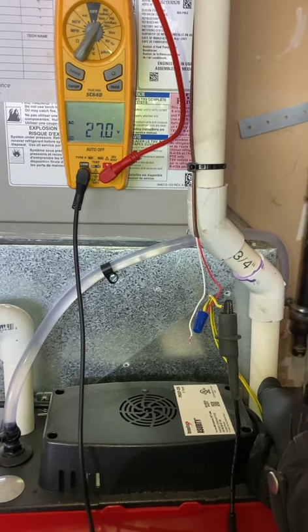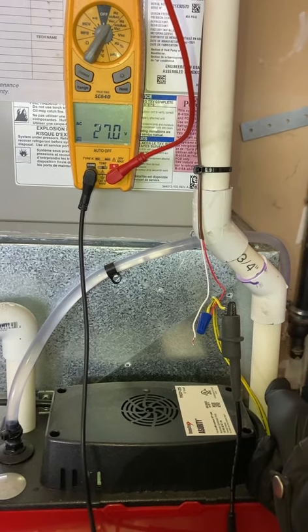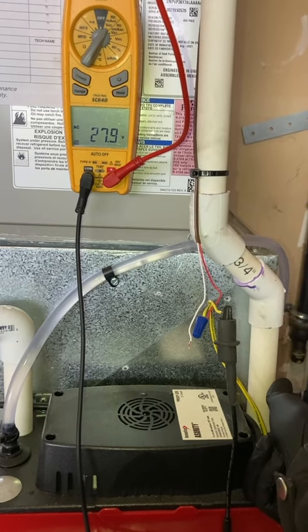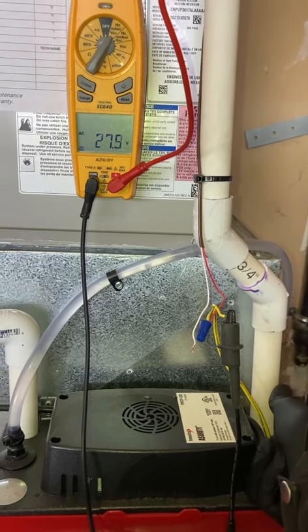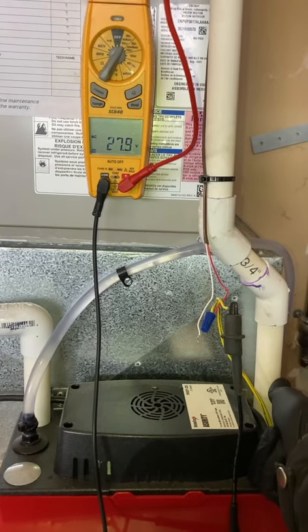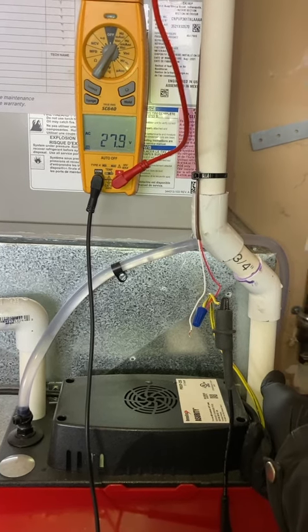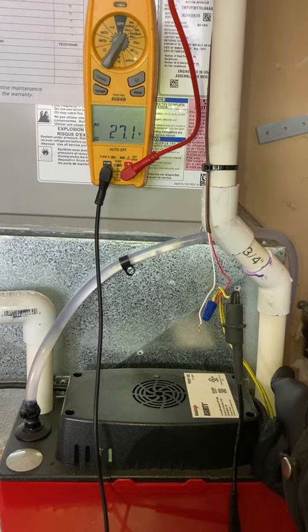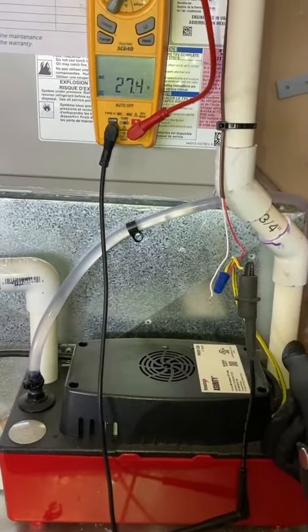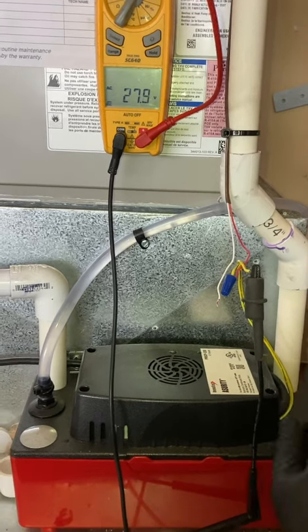It didn't drop any power at all — maybe one volt, dropped 0.9 volts. This is not going to interrupt the power of your thermostat. So even though it would test good under continuity with voltage going to it, it's actually bad. I'm guessing there's corrosion or something on the terminals — it's barely dropping any power at all.